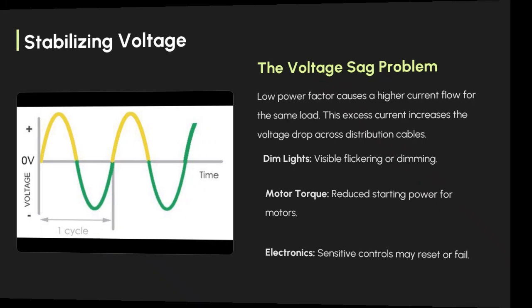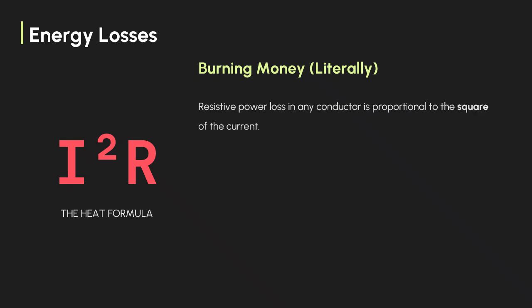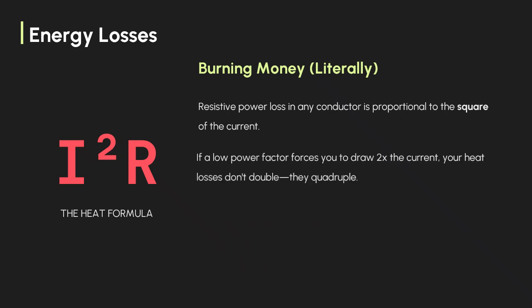Energy losses, physics. The financial implications of power factor are rooted in basic physics. Resistive power loss in any conductor is determined by the I²R formula, where I is current. This loss is proportional to the square of the current. If your low power factor forces you to draw twice the necessary current, your heat losses don't just double, they quadruple. This effect, often called burning money, is a direct drain on efficiency, which you are paying for through increased energy consumption.